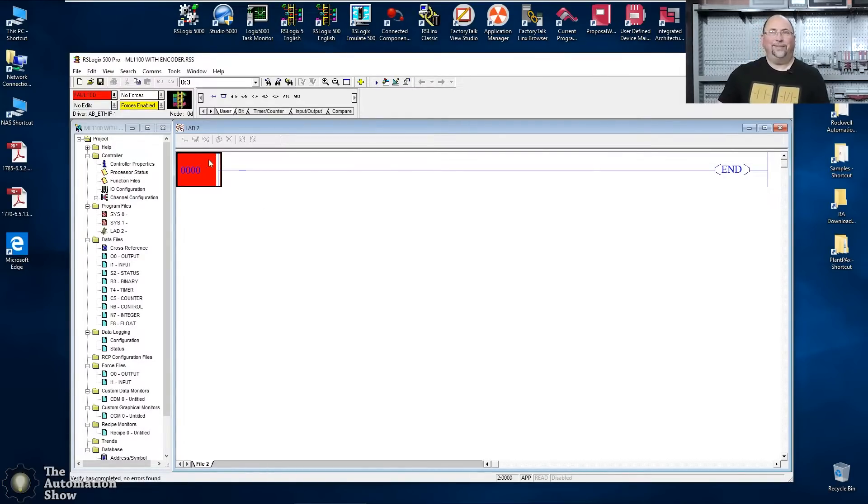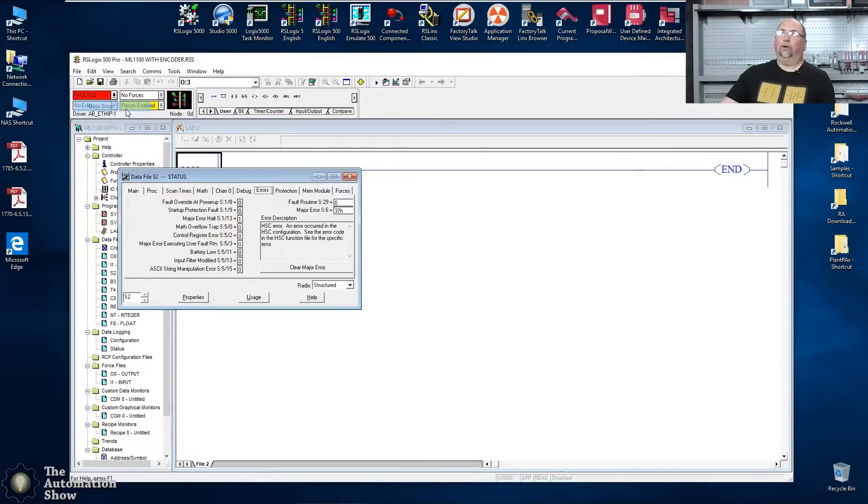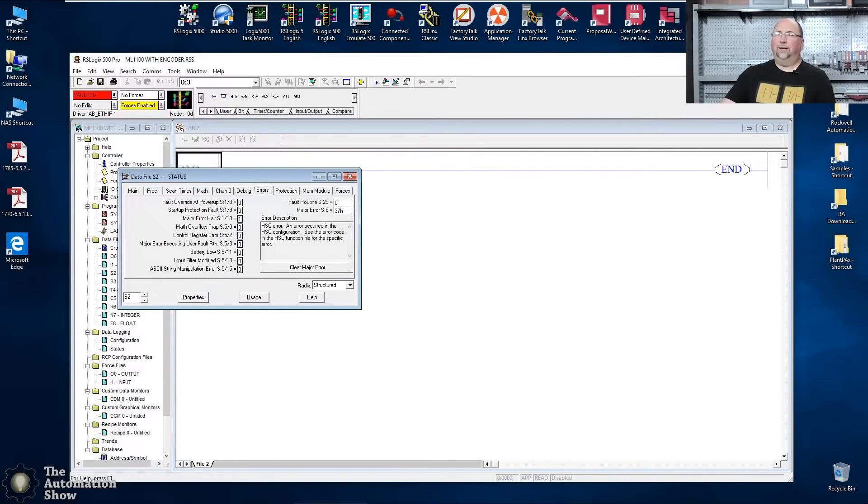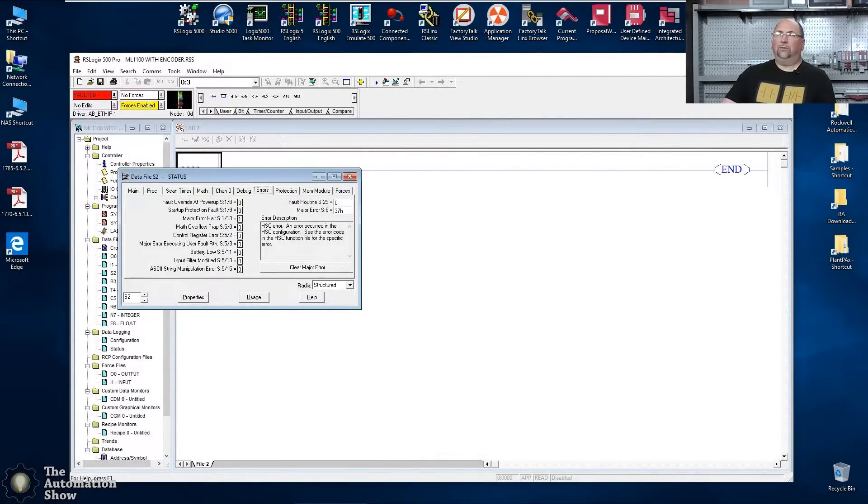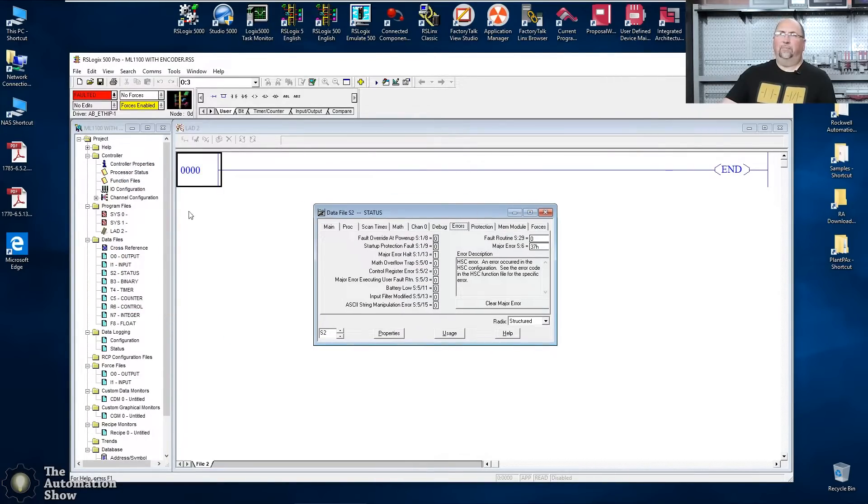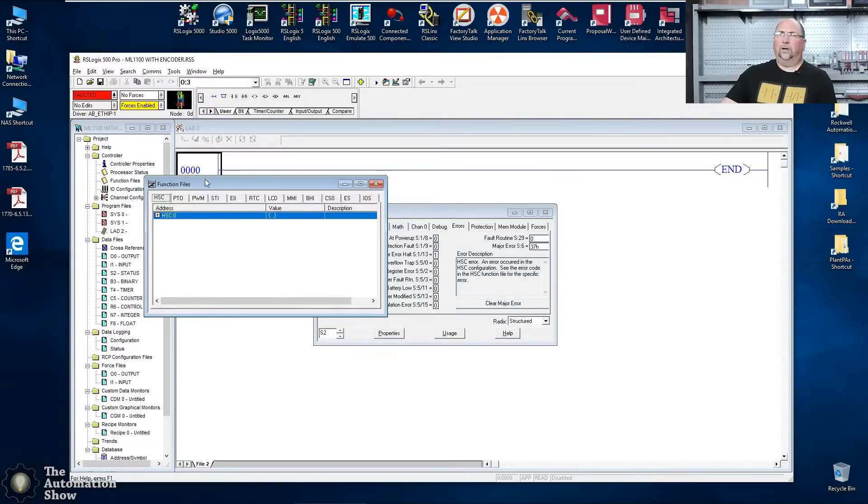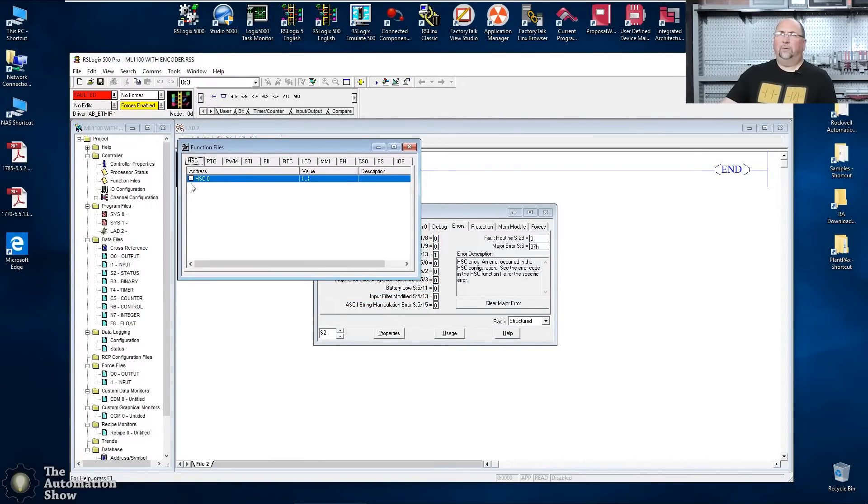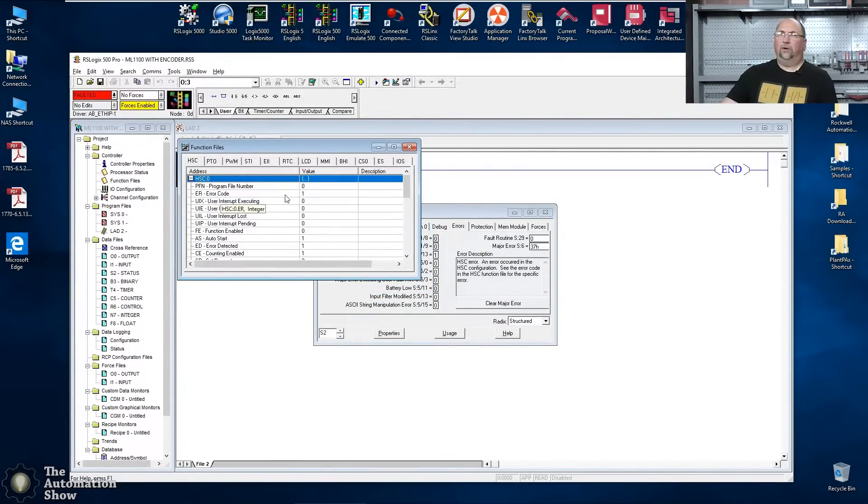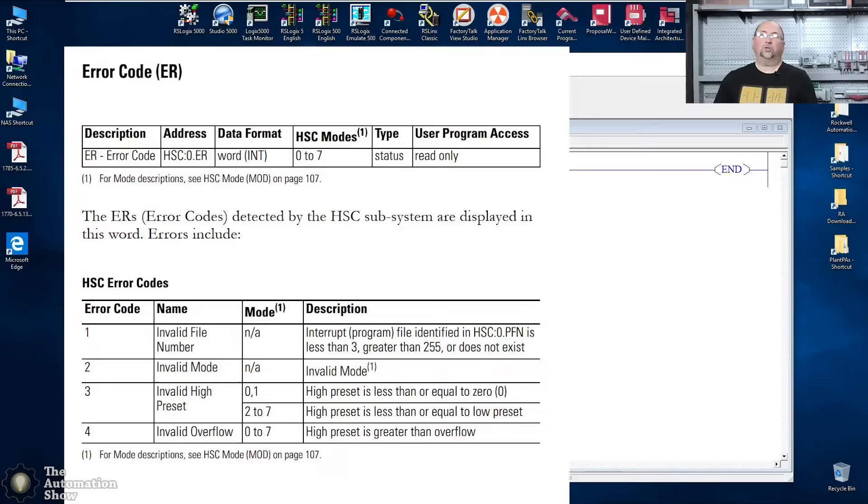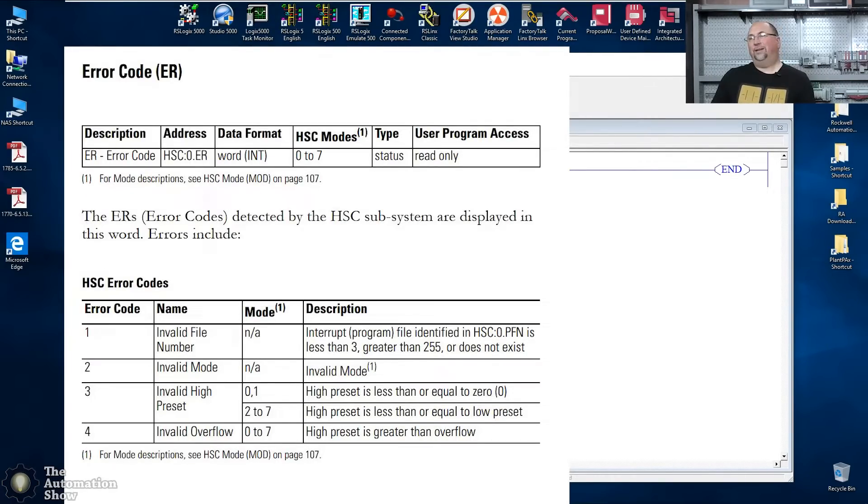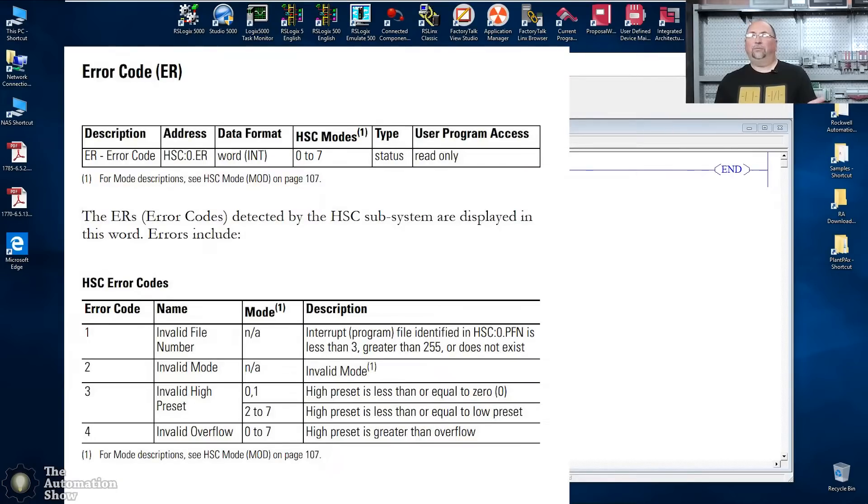Why is it faulted? This makes no sense, right? Well, let's go to the error and you can see here. Hey, go see the HSC error function file to find out what the error is. So I won't clear it yet, but let's see if we can go into the function file. And here we can see the error code is number one. And if I bring up the manual here and put that on the screen, you'll see that's because PFN doesn't have a value.